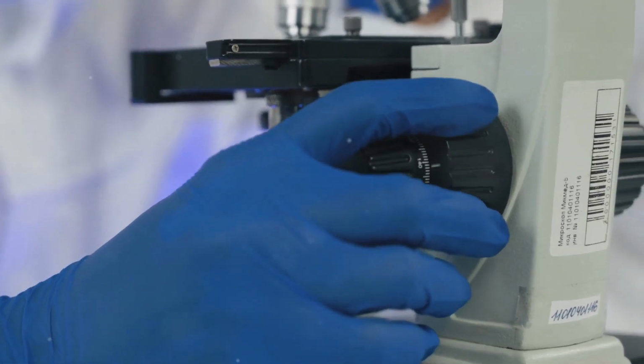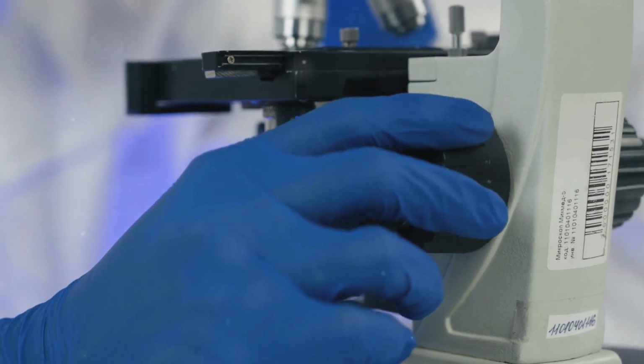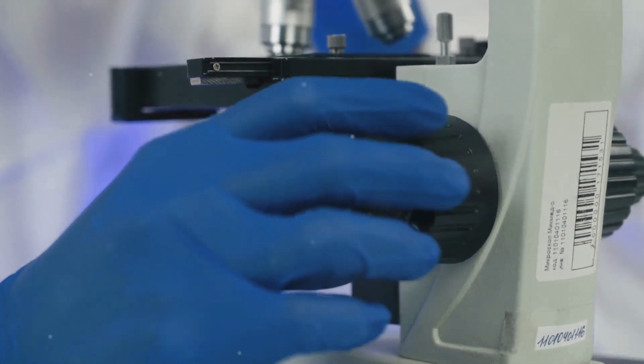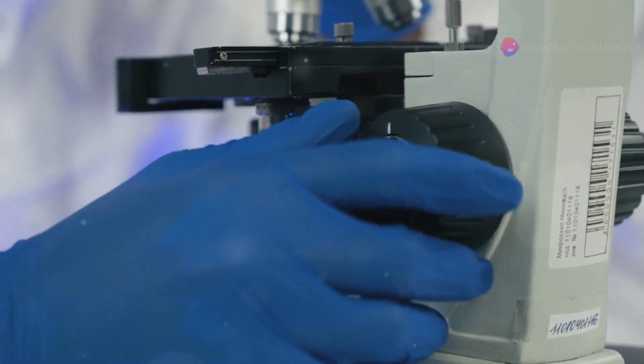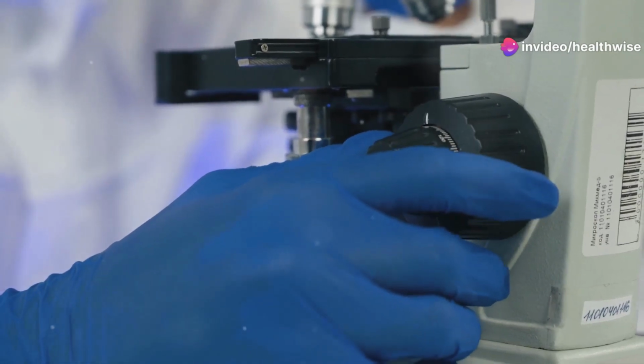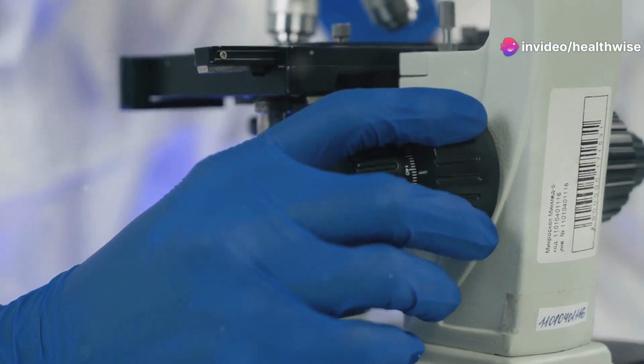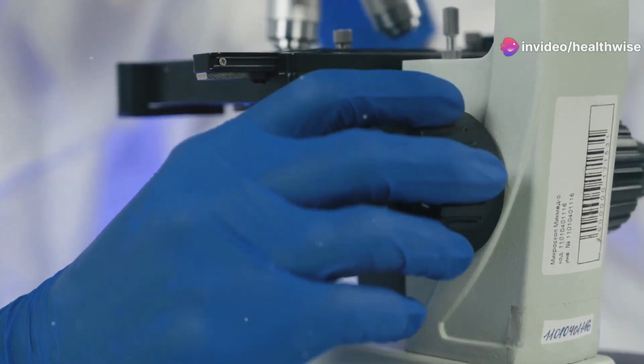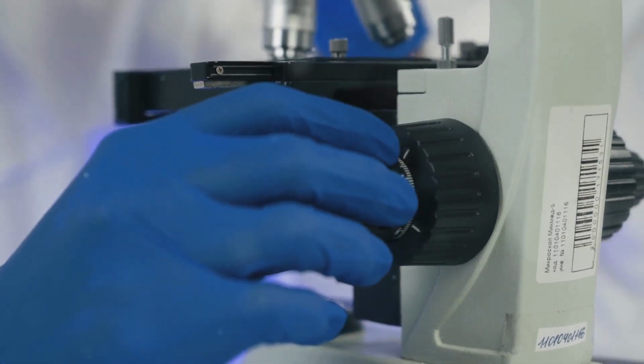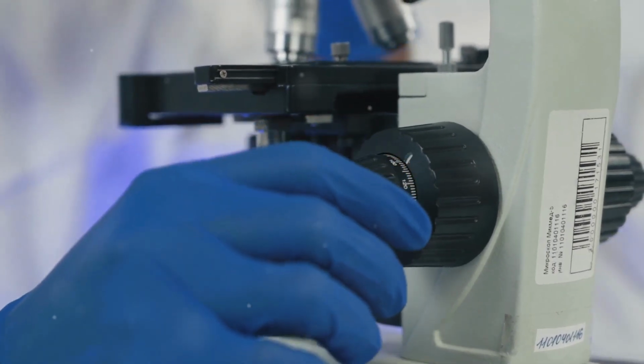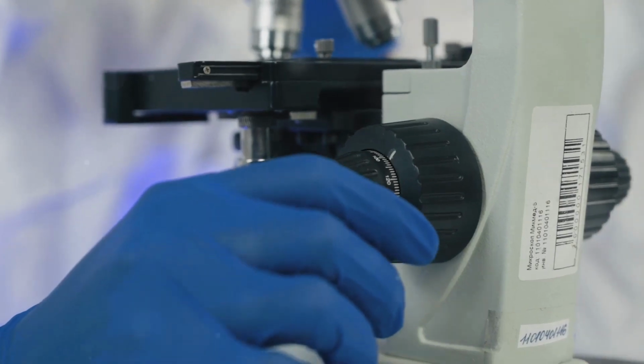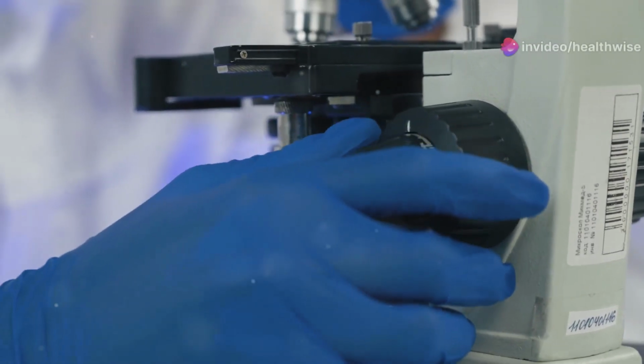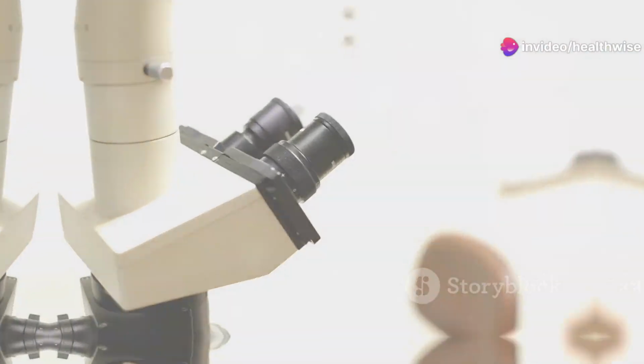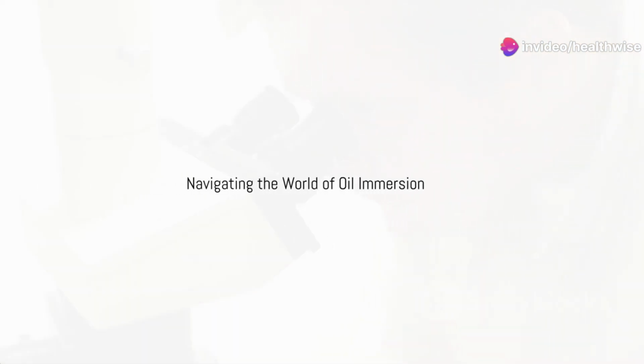The culprit? A slight discrepancy between the focal point of the high-power objective and the other objectives, a common occurrence, especially in student-grade microscopes. To remedy this, most microscopes are equipped with a diopter adjustment ring on one of the eyepieces. This ring allows for fine-tuning the focus of each eyepiece independently, compensating for any minor discrepancies between the objectives.